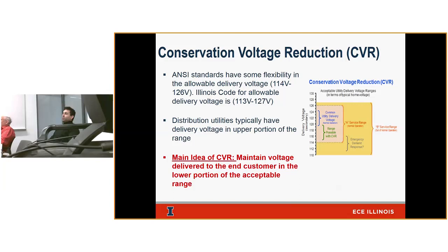Conservation voltage reduction — if you look at the ANSI range, it indicates the allowable delivery voltage to the end user. For 120-volt base, the ANSI range is 114 to 126 volts. Illinois had to be different, and our code here is 113 to 127. So Ameren Illinois and ComEd have to meet that 113 to 127 voltage range for our customers as a delivery voltage.